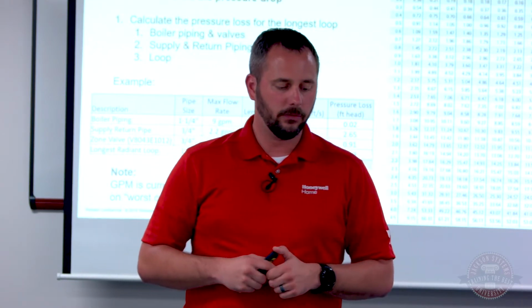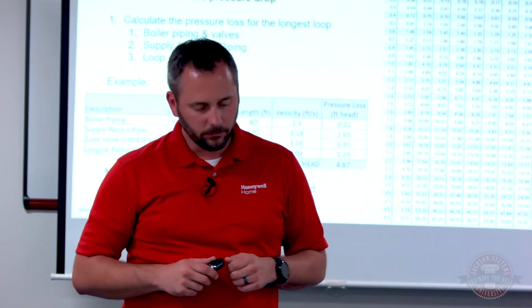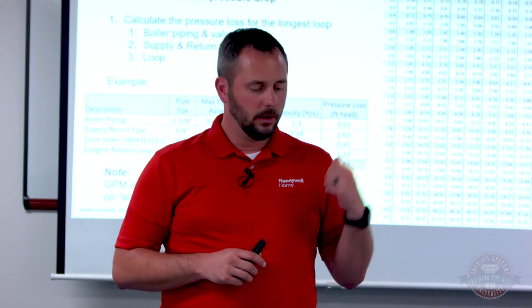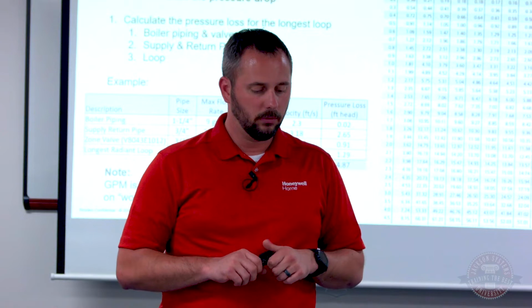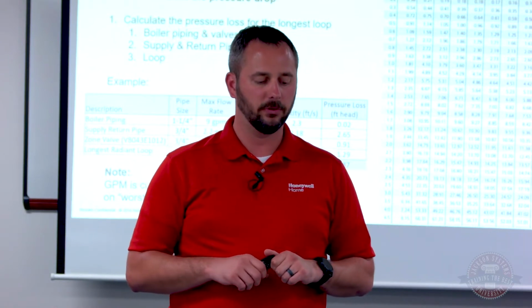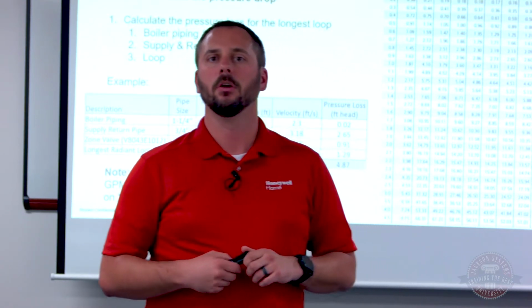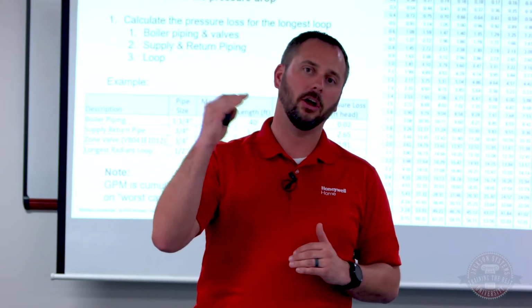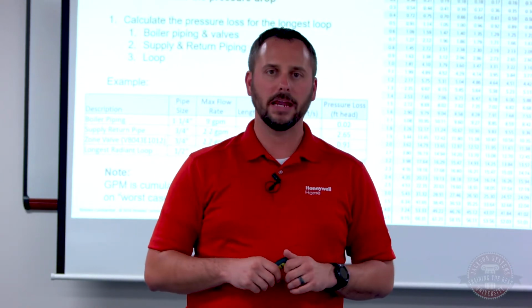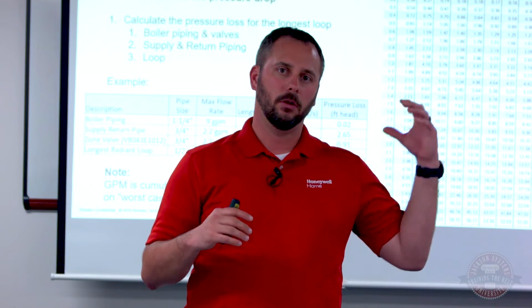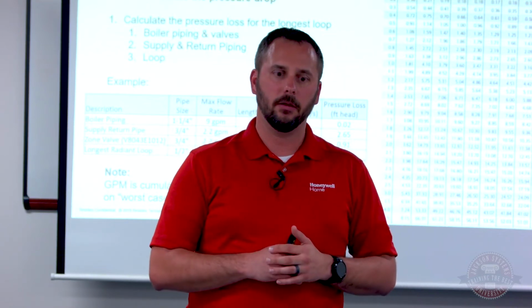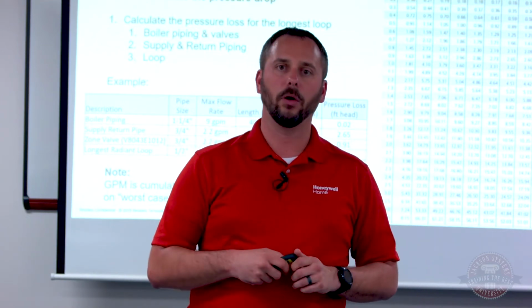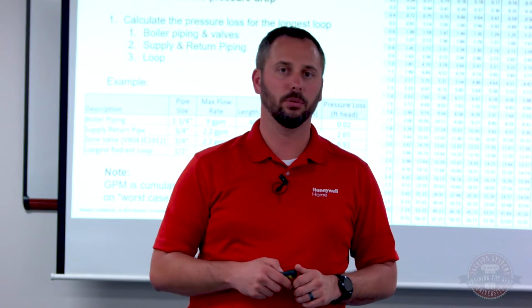The zone valve at 2.2 gallons a minute is 0.91. And then we've got the longest radiant loop, which is only 1.29 because that loop is only doing 0.6 gallons a minute. So your system designs will kind of tell you where you need to be, but we're breaking it down. So that system, again, we're looking at 9 gallons a minute on the flow rate. We're looking at 4.87 feet of head. So very, very simplistic system.